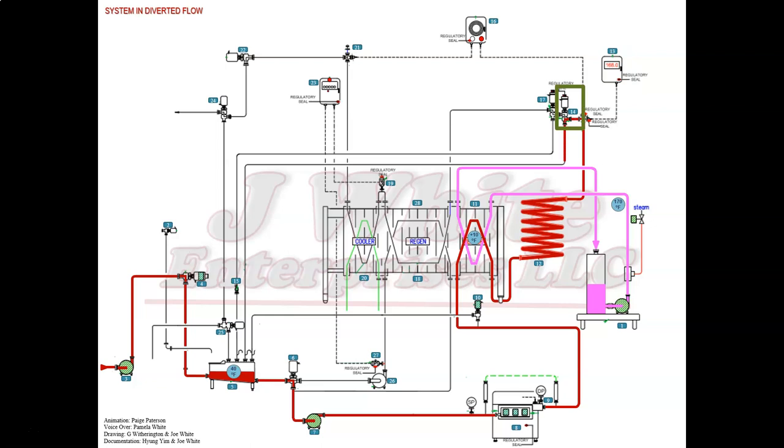The flow divert valve is de-energized when product temperature is below pasteurization temperature, so the product will return to the balance tank in diverted flow.